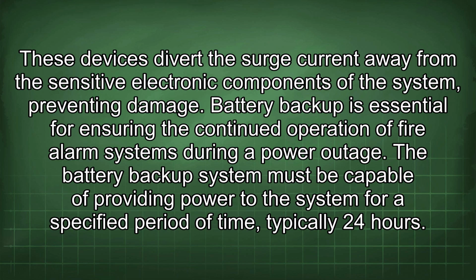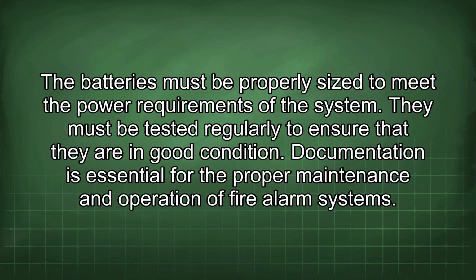Battery backup is essential for ensuring the continued operation of fire alarm systems during a power outage. The battery backup system must be capable of providing power to the system for a specified period of time, typically 24 hours. The batteries must be properly sized to meet the power requirements of the system. They must be tested regularly to ensure that they are in good condition.